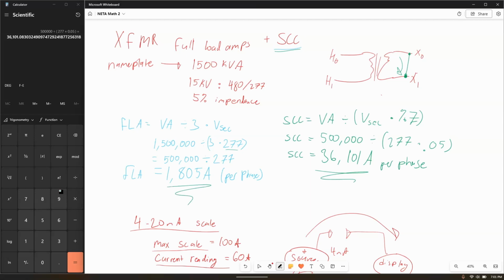The full load amps is the amount that the manufacturer has designed the transformer to run for. Our short circuit current is the amount that would theoretically happen if I had a bolted short circuit fault between X0 and X1, right on the secondary stab of the transformer. That would be probably worst case scenario, but this is important because this is a number that we have to use when we're sizing things like fuses, sizing breakers, or most importantly for our line of work, this is the formula that we're going to use to make sure that we have the right size personal protective grounds when we're working on the low side of a transformer, whether we're at a substation, industrial facility, something like that. This is going to tell us what size grounds we have to hang in order to be safe working downstream. So really, really important stuff to keep in mind.